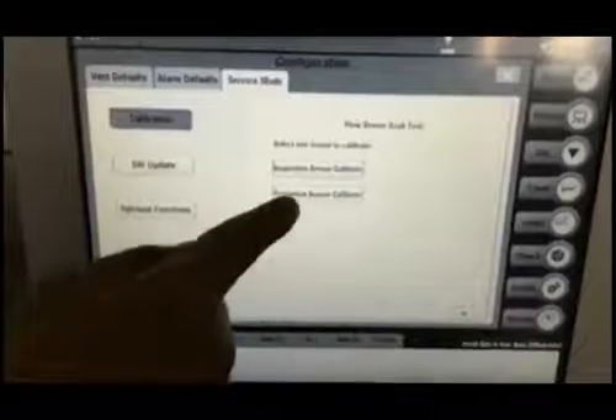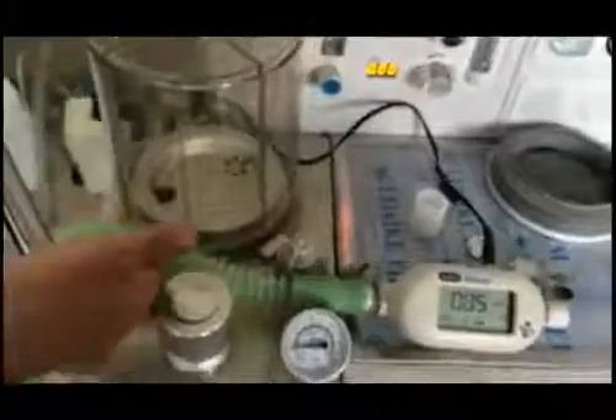Now we will perform the expiration sensor calibration. In order to perform the expiration sensor calibration, the first step is to select the expiration sensor calibrate key on the screen. Please read the instructions. The first instruction is to remove the inspiration and expiration valve discs. As shown, we have already removed them.